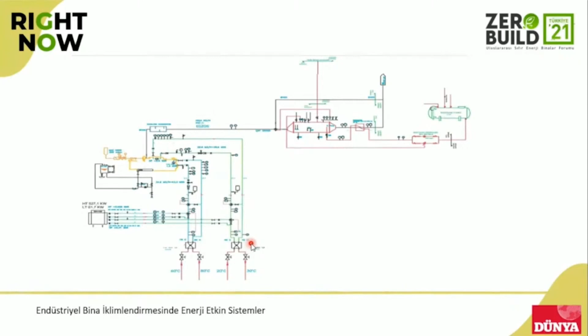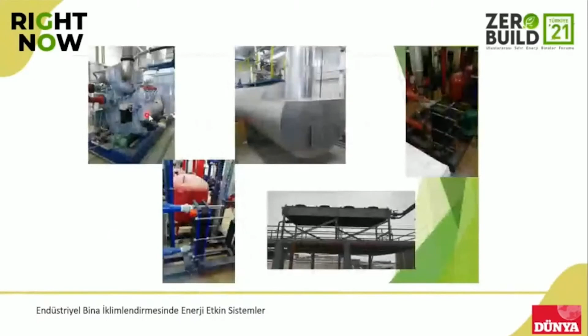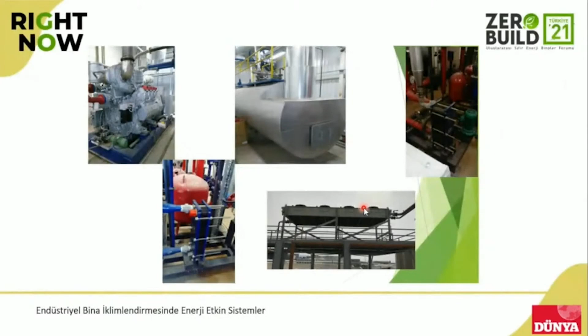4,500 kilograms of flue gas is given to this steam system, providing steam at 300 kilowatts per hour. This gas engine has one cooling jacket and another after-cooling or turbo element. When we combine it with plated exchangers, we can have a combined 500 kilowatts of energy. Here you see a gas engine, waste heat boiler, exchangers, and if they fail, a radiator. Our analysis shows it can work with 86% efficiency.